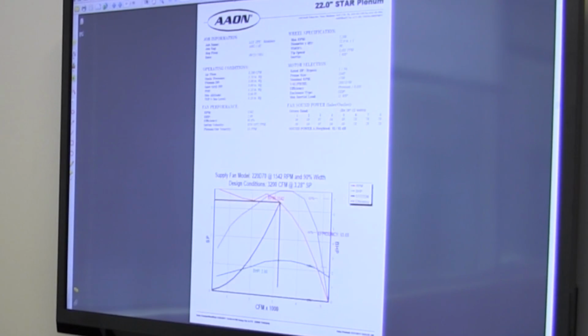And when you put an amp probe on that, it's crazy. You watch it, and one second it says 9 amps, and the next second it says 60 amps. It really is pulling current, not pulling current. If you attach that unit straight up to a generator, for instance, it'll cause havoc on that generator, just because that truly is how it's supposed to work when you're measuring it. You'll see the same thing on that digital scroll as it modulates your pressures. Your pressures change each time it cycles, your amperage changes, the sound changes.